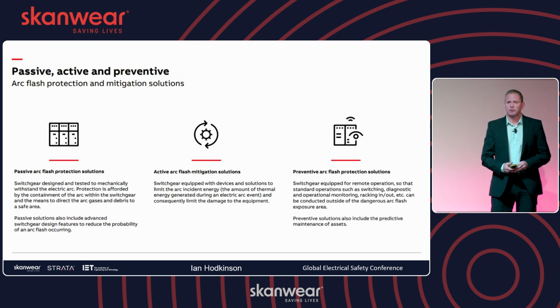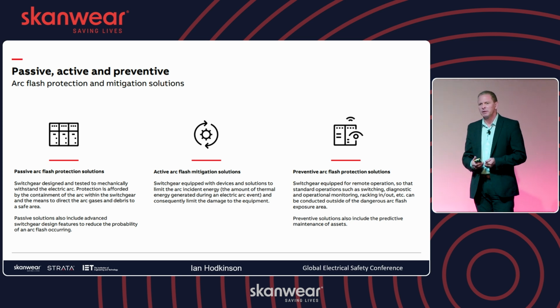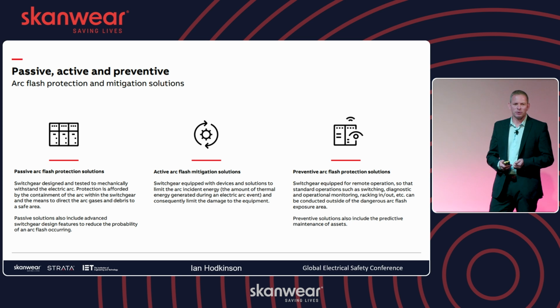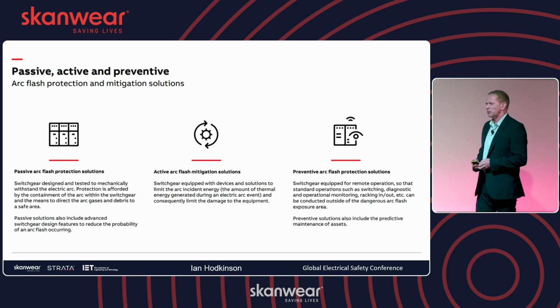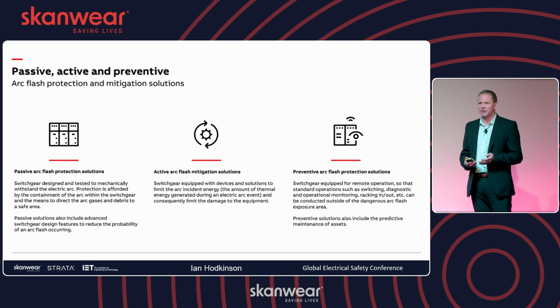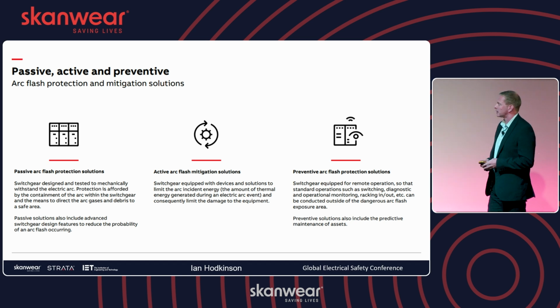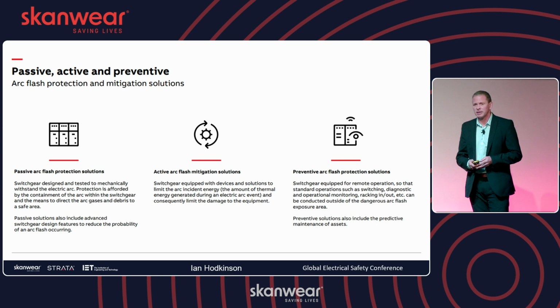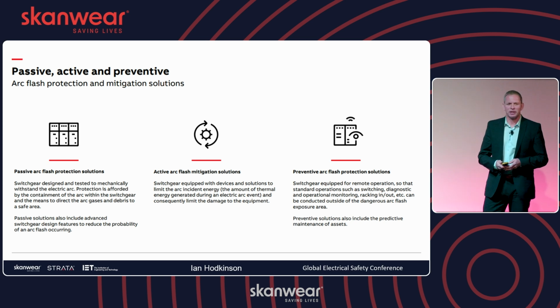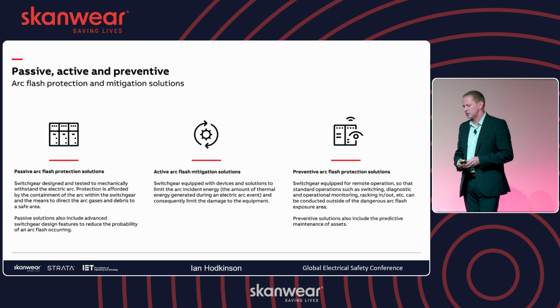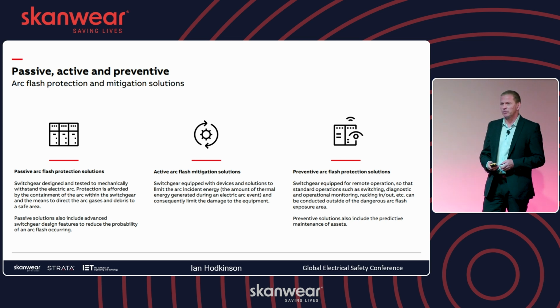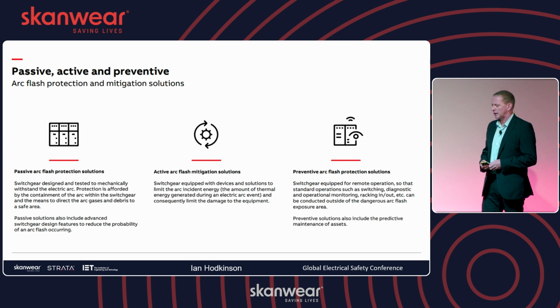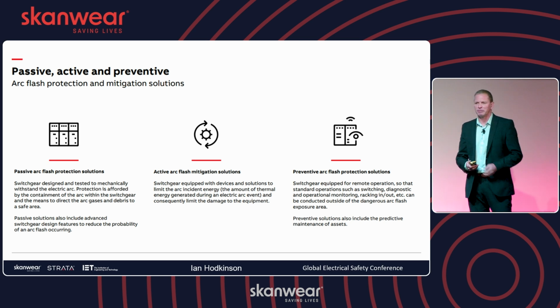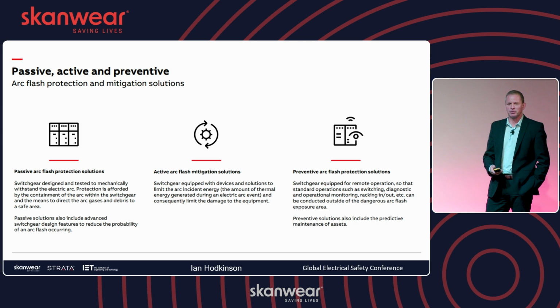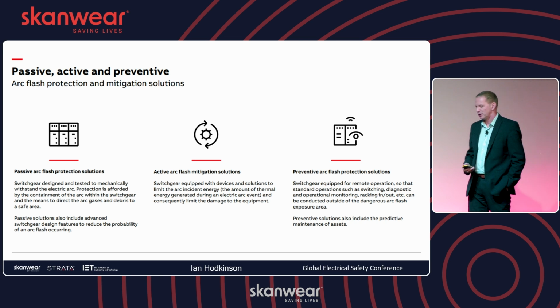First of all, as mentioned yesterday too, you need to design arc protection into your switchgear. We call that passive protection: if your switchgear is designed to internally contain that arc, that's a positive step at the design stage. Secondly, you can mitigate using active protection to reduce energy levels and reduce the time to clear the arc. Further still, you can put preventative measures in place to help avoid that arc incident in the first place.